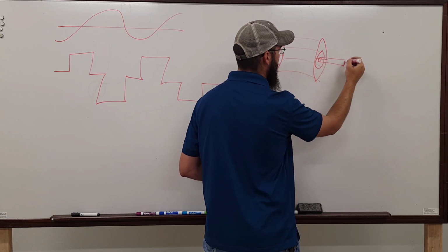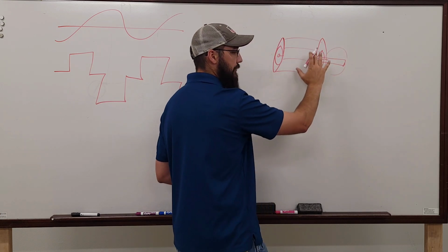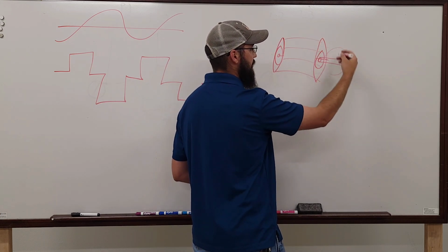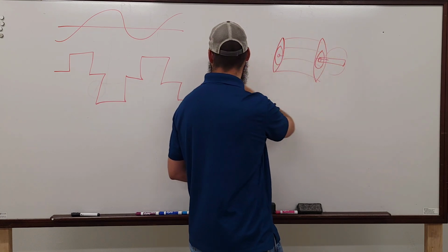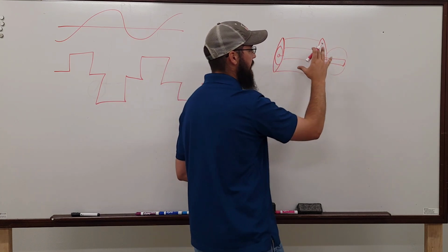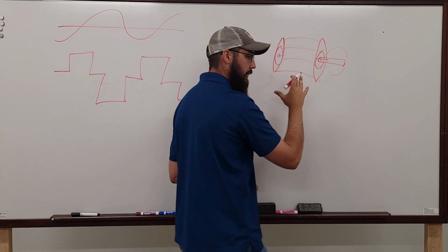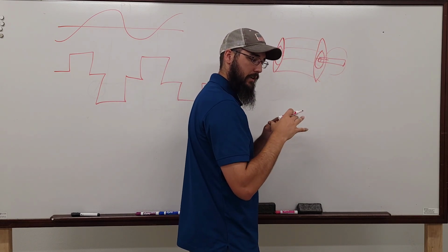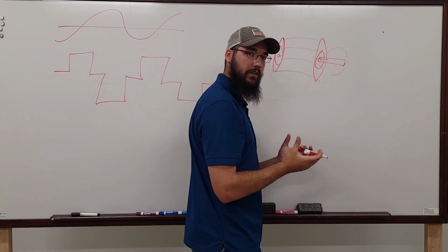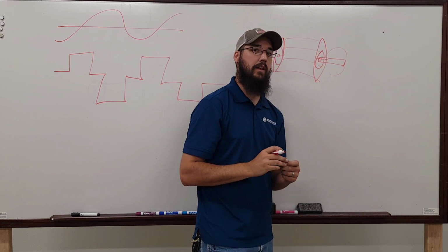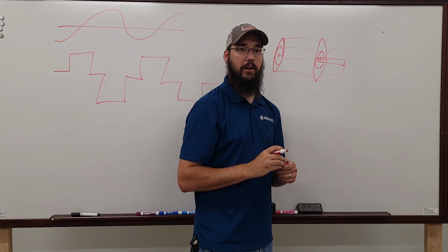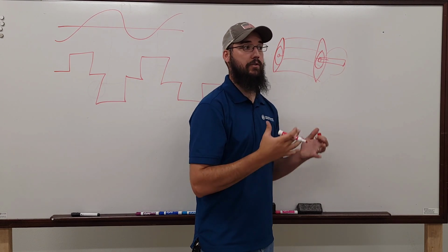While this is rotating, and the magnetic fields are being produced to modulate the speed, the pulse width wave is actually inducing, through its harmonics, a physical charge inside of that rotor, to where that rotor is actually becoming electrified.